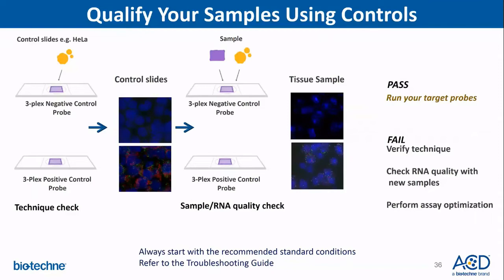Once you perform the technique check using the control slides, the next step is to do a sample RNA quality check. So you would run those negative and positive control probes on your target tissue. Once the target tissue passes QC, where the RNA quality is good, then you may go on to run your target probes. If this fails, then we recommend that you verify the technique using control slides, check RNA quality with new samples, and perform optimization if needed.